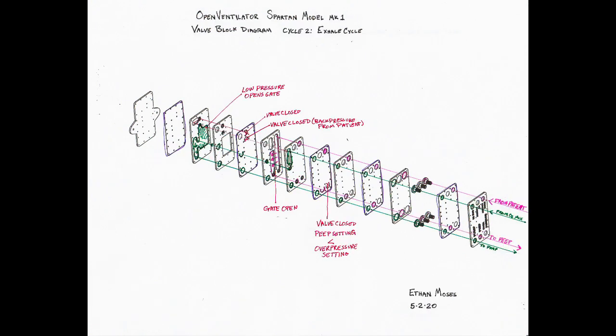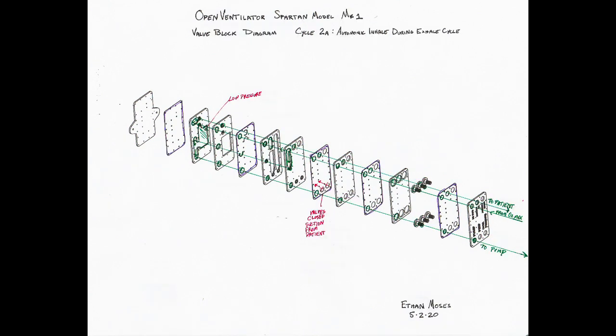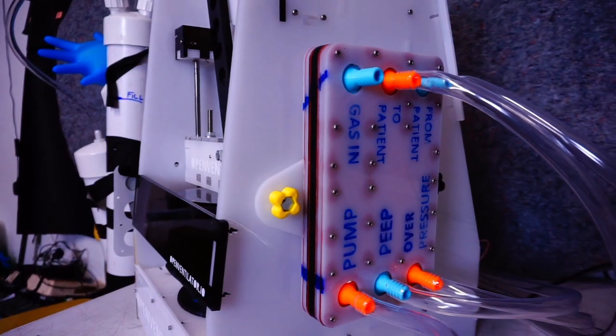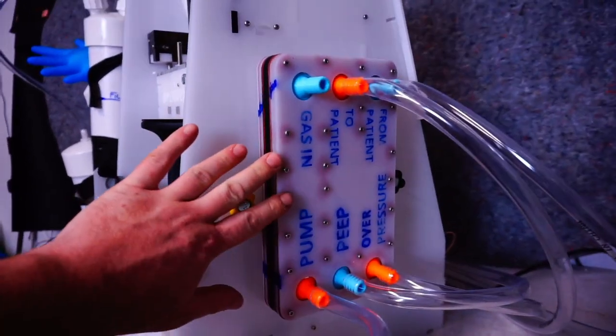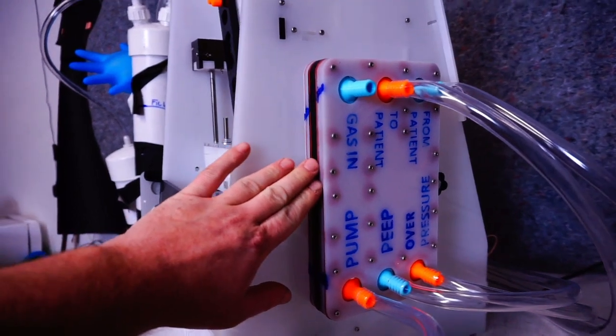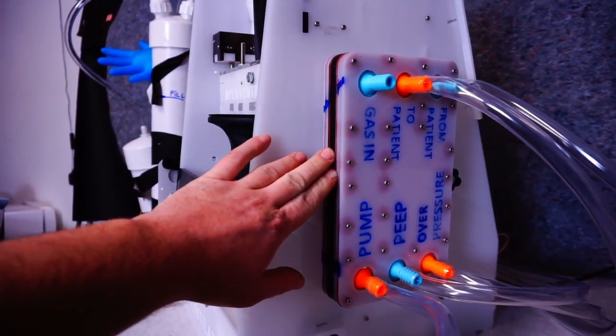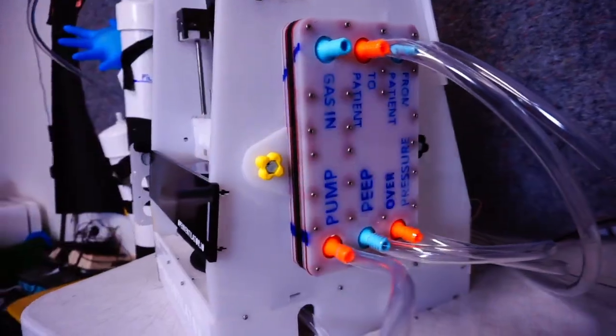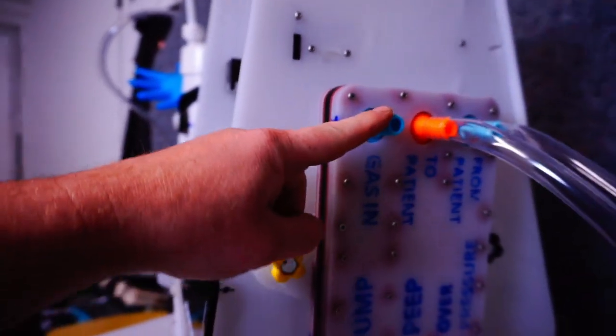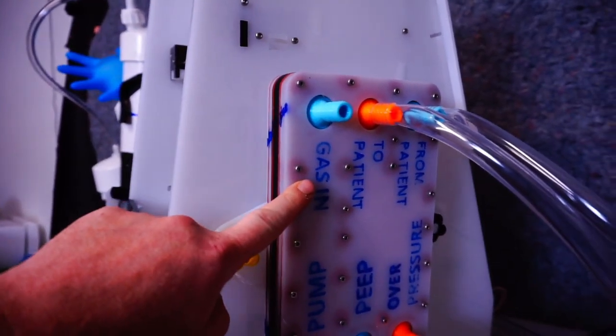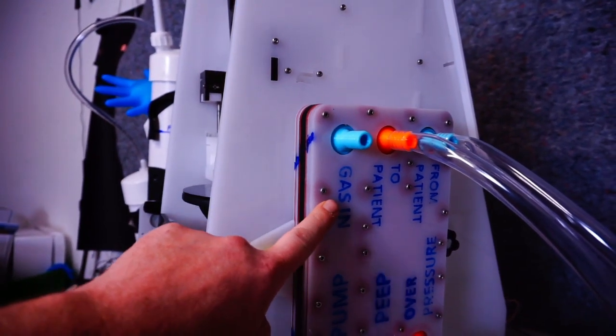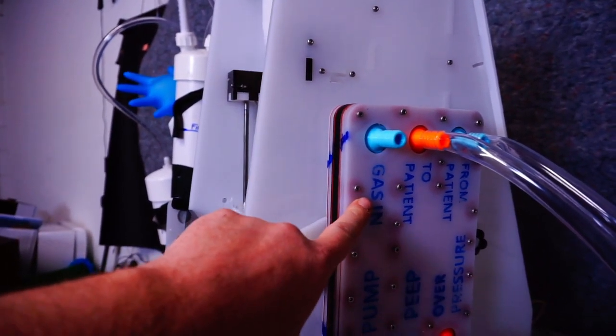Traditionally, a lot of this work would be digital logic using things like pressure sensors, microcontrollers, and solenoid or other electronic or electromechanical valves. Our solution just uses pressure and a bunch of different interacting valves to accomplish the functions of the ventilator during its cycle. Let's take a look at the ports. This port is gas in. Not in the scope of this project is a Venturi mixing valve that mixes oxygen and intake air.